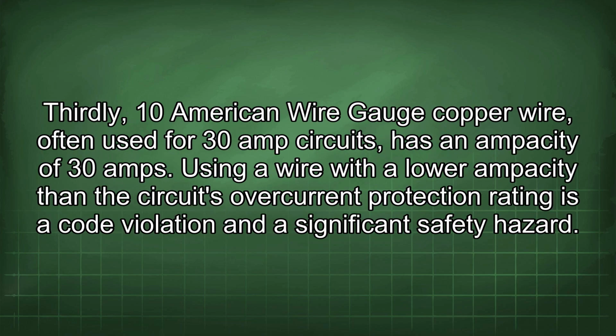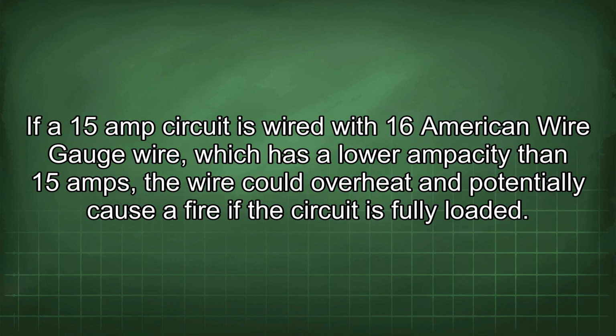Thirdly, 10 American wire gauge copper wire, often used for 30 amp circuits, has an ampacity of 30 amps. Using a wire with a lower ampacity than the circuit's overcurrent protection rating is a code violation and a significant safety hazard. If a 15 amp circuit is wired with 16 American wire gauge wire, which has a lower ampacity than 15 amps, the wire could overheat and potentially cause a fire if the circuit is fully loaded.